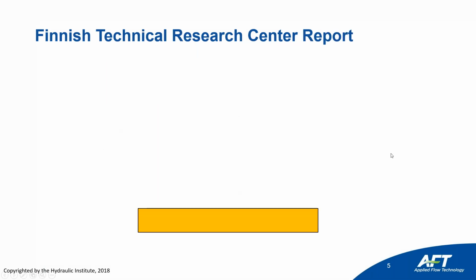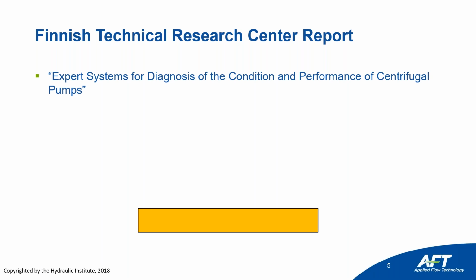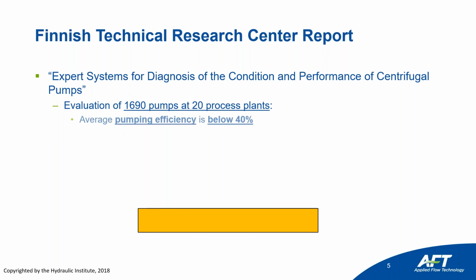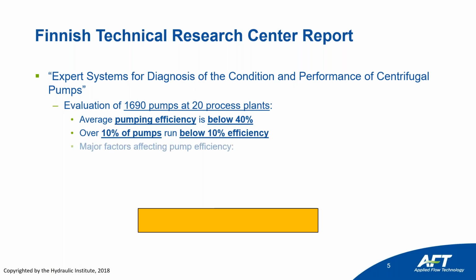And so this is a technical report that a Finnish company did several years ago. It's called Expert Systems for a Diagnosis of the Condition and Performance of Centrifugal Pumps. What they did is they evaluated just about 1,700 pumps across 20 different process plants. Here's what they found. On average, the pumping efficiency for those pumping systems was below 40%. So very, very inefficient operation there. Another issue is that they found that over 10% of those pumps were even running below 10% efficiency. So again, just throwing money right out the window.